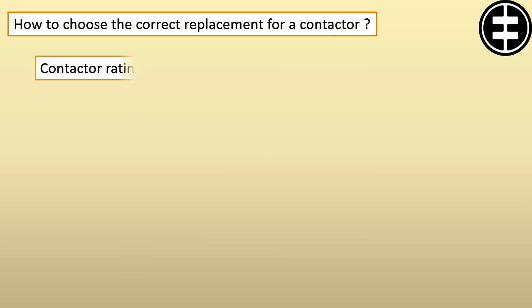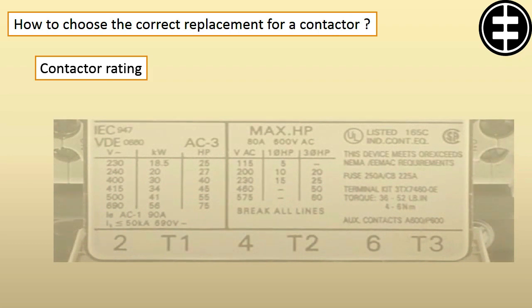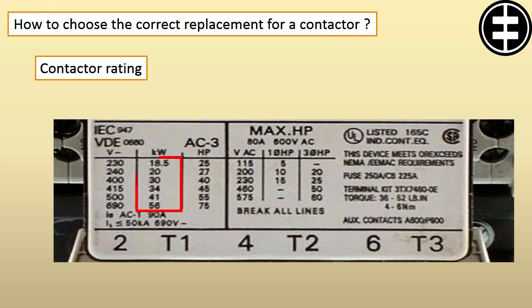Third, check the contactor rating. It is the contactor's designed capacity, and it is printed in a table on the contactor. If we check this contactor table, it is written from 18.5 to 56 kW. Which one is the contactor rated? It depends on your load. If your load is a motor, you have to check the AC3 table. Then say your power network voltage is 400 volts, that means this contactor rating is 30 kW.